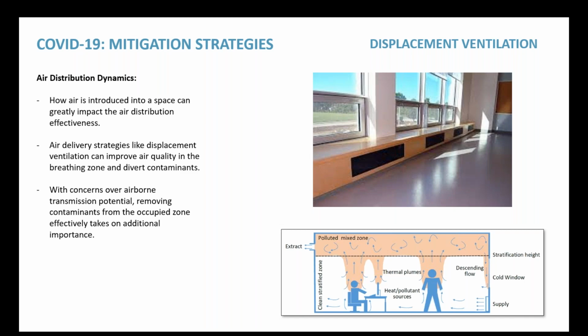And the effects of this can be seen in the way that we calculate outside air requirements. So for this type of system, when you're doing your outside air totals via Standard 62 calculations, it actually gives you an air distribution effectiveness factor of up to around 1.2.